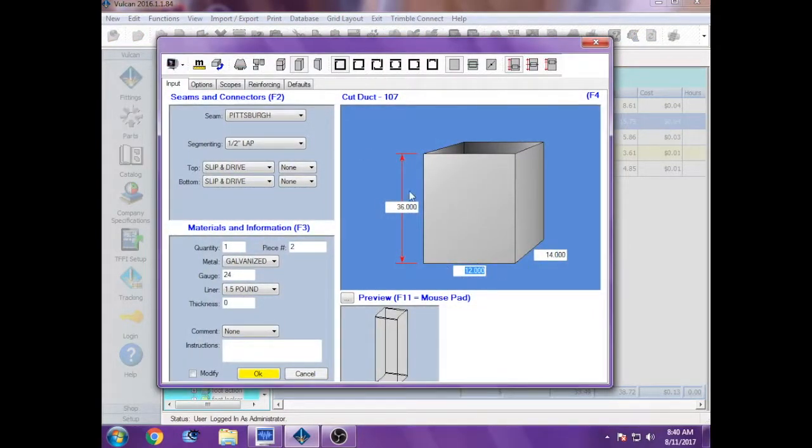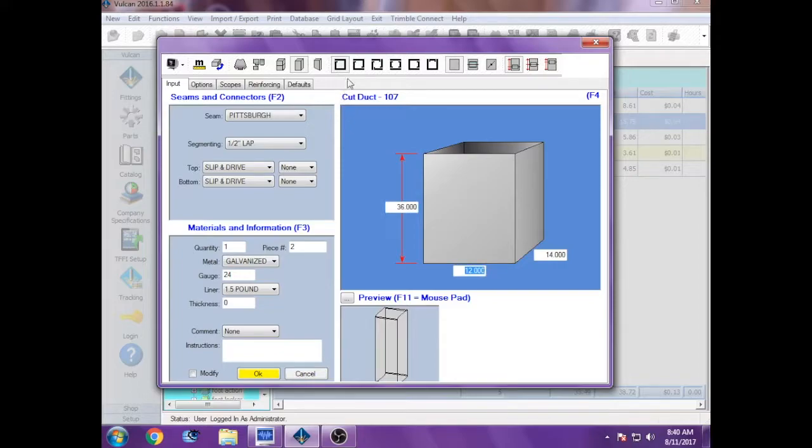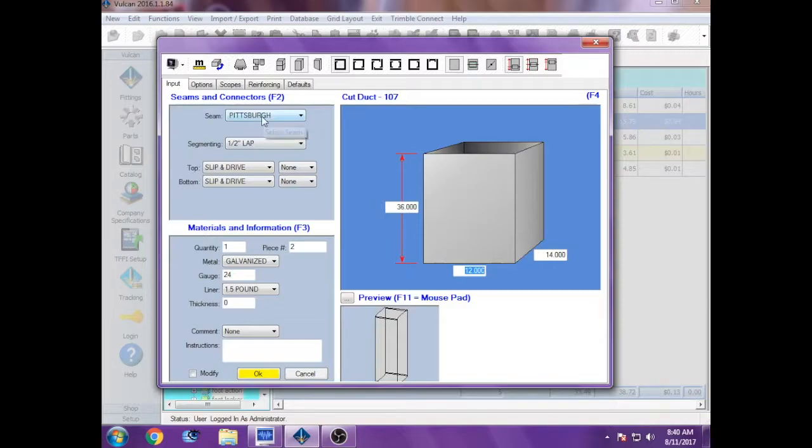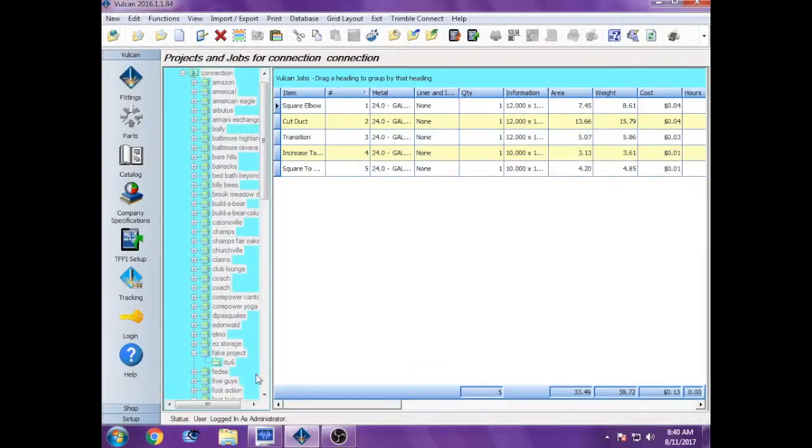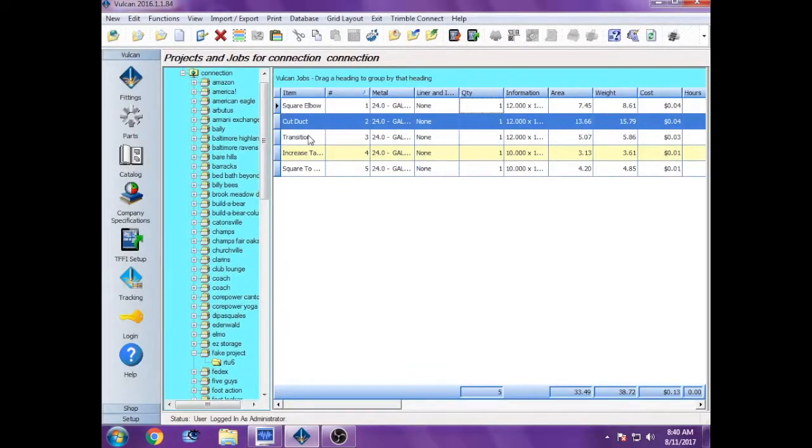Piece number two is a piece of cut duct, and that's just 12 by 14 that's three foot long, 36 inches long. You have to always enter it in based on inches, not feet. Whenever you can, you want to make it one-piece wraparound for cut duct. Same kind of connection, Pittsburgh slip and drive, 24 gauge, hit okay.